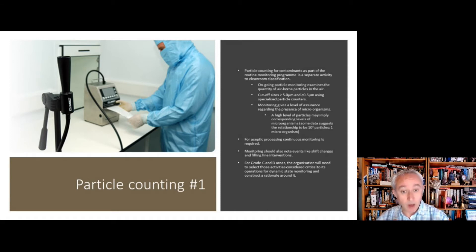Although monitoring determines the level of these ostensibly inert non-viable particles, such monitoring also gives a high level of assurance regarding the presence of microorganisms. A high level of particles may imply a corresponding level of microorganisms, but that depends upon the origin of the particles. For example, if we've got metal grinding upon metal, it's unlikely those particles are going to be microbial. However, if we've got poor personnel practices, there's a good chance that they are microbial.